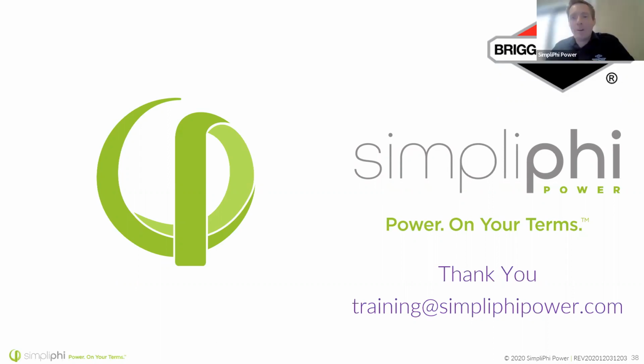Good point. So my answer to your question is look at how much you can continuously draw out of the batteries, even if it's a surge, and you can size based on that. There's nothing wrong with doing that. But pay attention to the surge and, as Chuck said, the inefficiencies. Look at the maximum that your equipment can draw. Remember, that's on the DC side of things, so it will be drawn at nominal 50 volts.